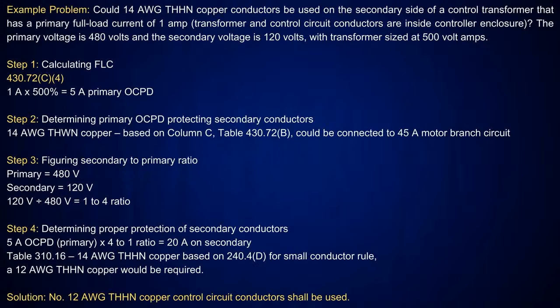So if I go over and look at table 310.16 and tie it in with 240.4(D) for my small conductor rule, it's going to tell me that number 12 copper conductors would be required instead of the number 14.